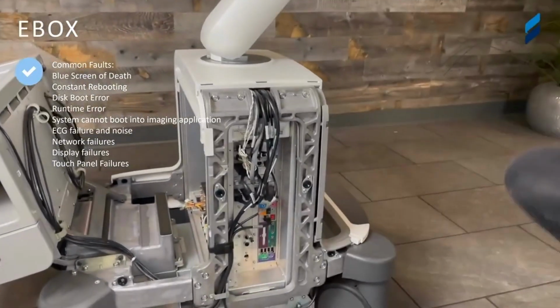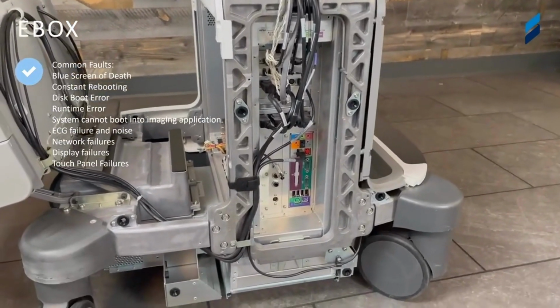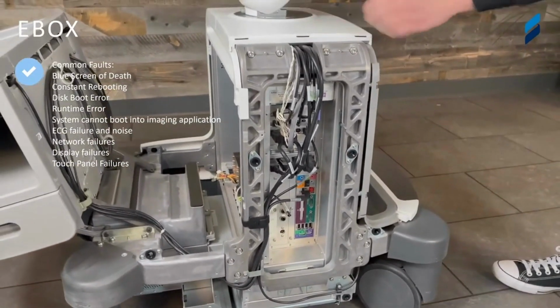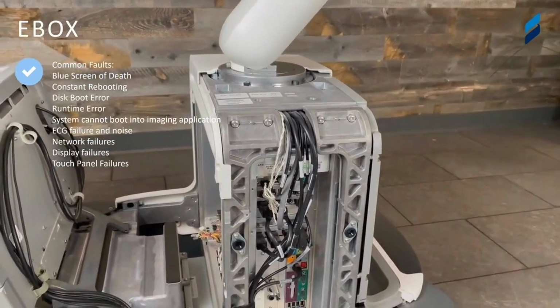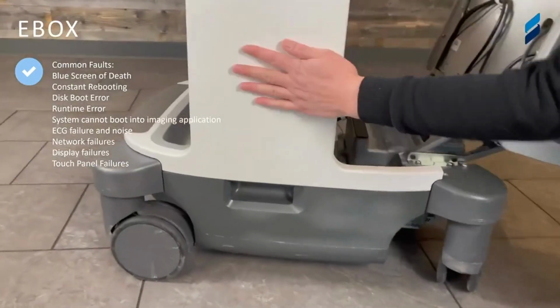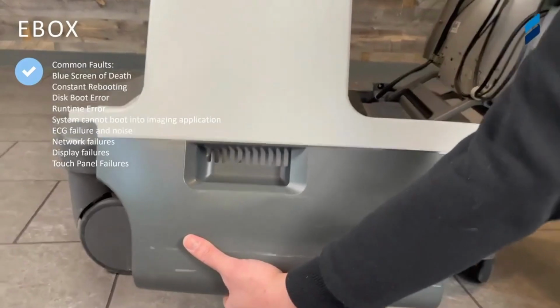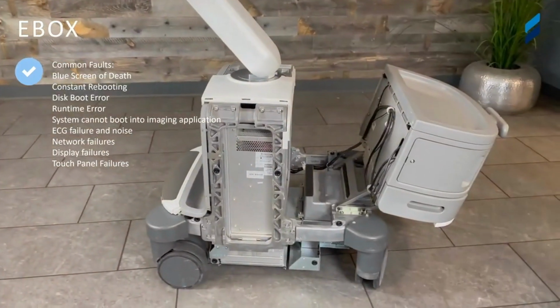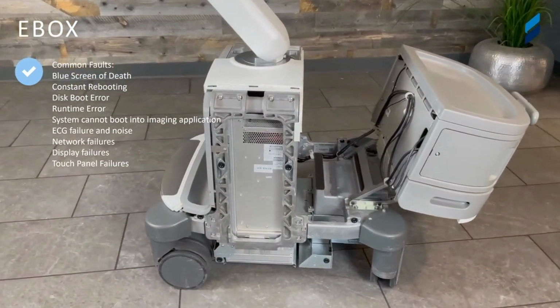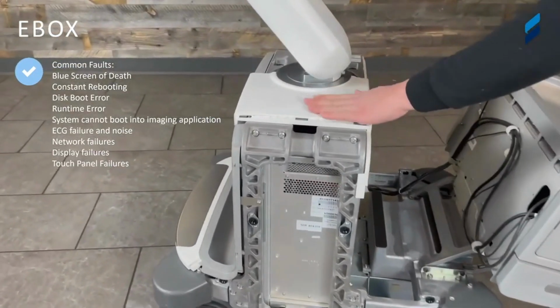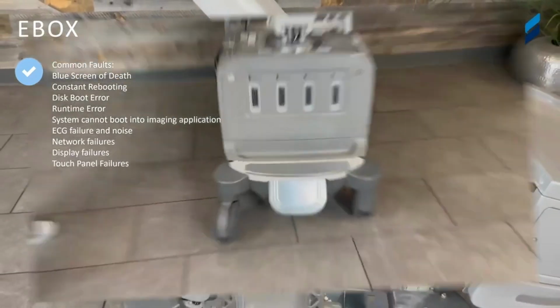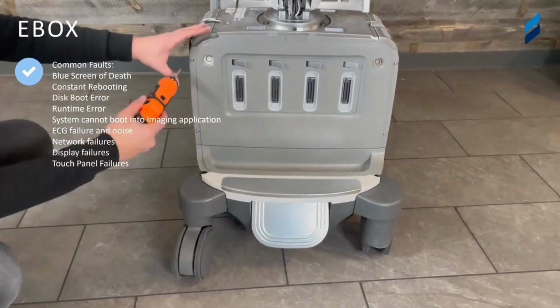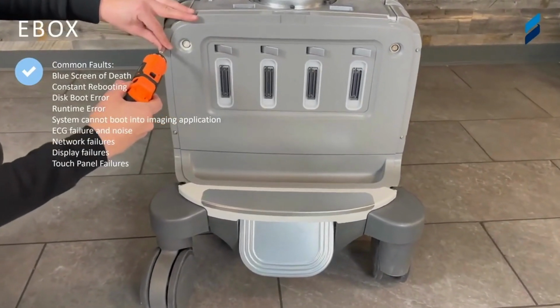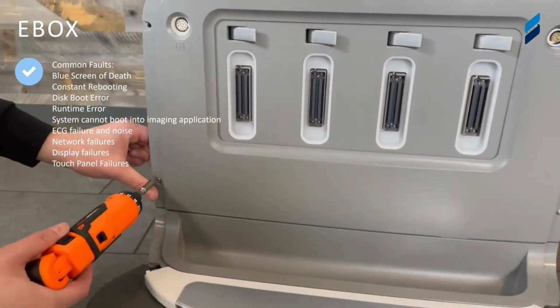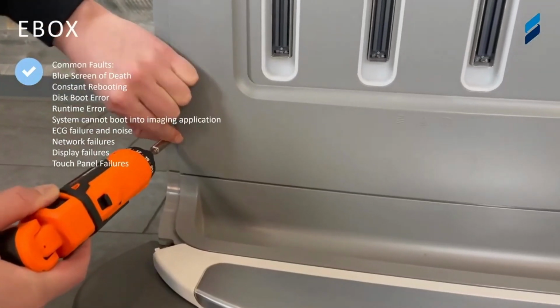This is your fan filter. So during your PM, go ahead and remove this. Make sure it's clean. We want as much fresh air getting into the internal of the system as we can. Side piece pulls off. It's just held on by those rubber clips. We're going to pull off and snap off the top white cover of the Ebox assembly. And we're going to do the same to the other side. The other side pops off. Unclip the top plastic is next. Now we have to remove the front. And so now we're going to get to the plastics and remove this front plastic.